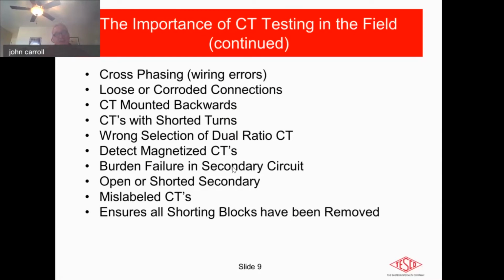And in some cases with these, the concern is that it's not a catastrophic failure we're looking at, so it's not really visible. That's the difficulty with this sometimes, that it's not always a visible condition that you're seeing unless you measure it. So that's why it's also important to keep control over these and have a program where you certainly look at these conditions under these CTs and customers themselves.